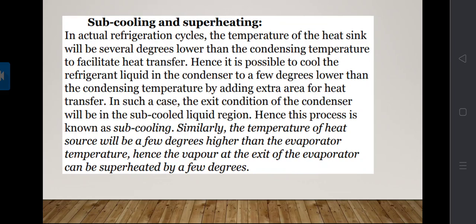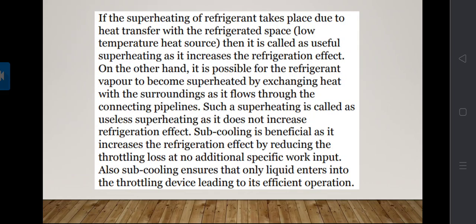Similarly, the temperature of the heat source will be a few degrees higher than the evaporator temperature, hence the vapor at the exit of the evaporator can be superheated by a few degrees. Superheating of the refrigerant due to heat transfer from the refrigerated space is called useful superheating, as it increases the refrigeration effect.